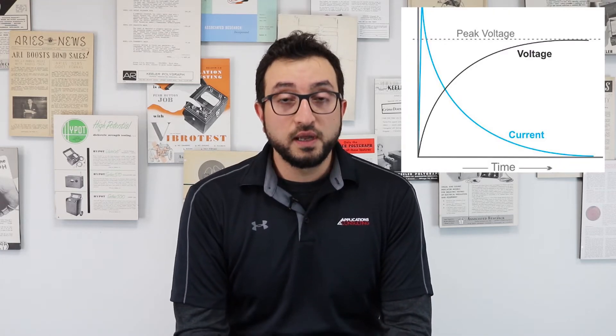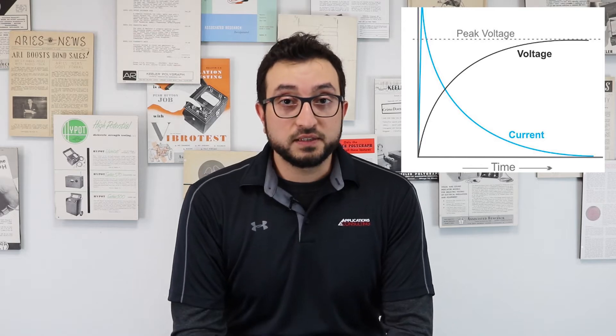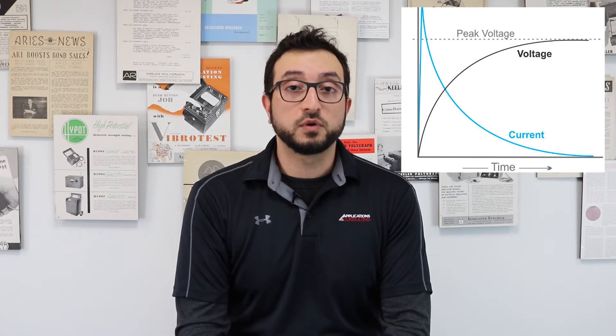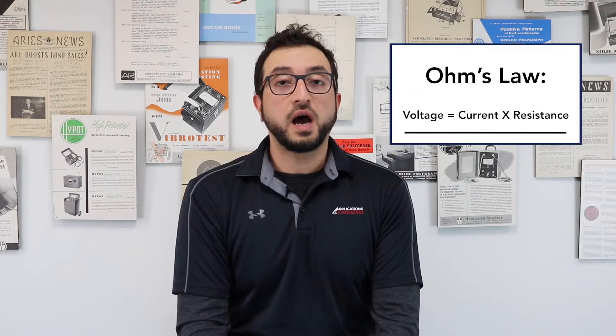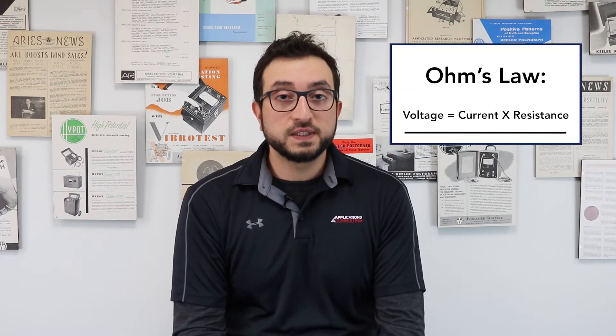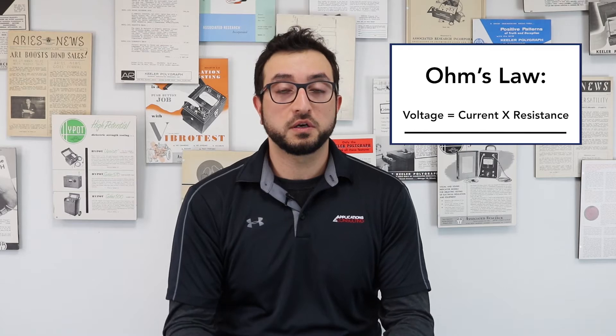That voltage results in a charging current that flows from the IR tester to charge the product's insulation. Once the capacitance of the product's insulation is fully charged, the only current that flows in the circuit is due to the resistance of the product's insulation. This is called the real current, and it is very small in value. The IR tester then uses this small real current value to calculate back the resistance of the product's insulation.